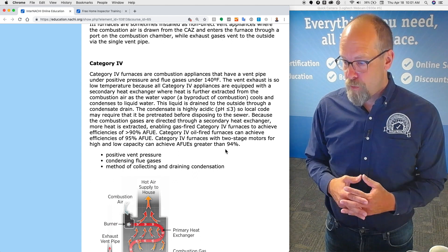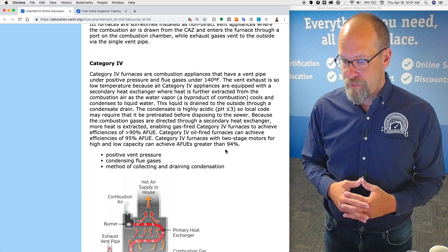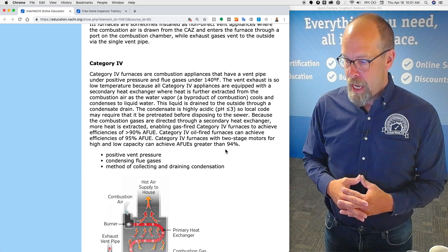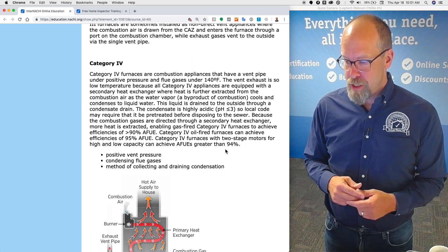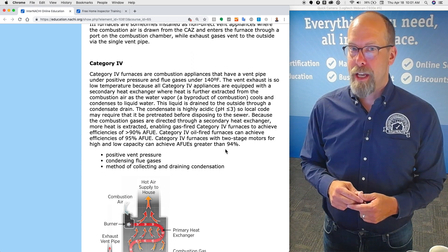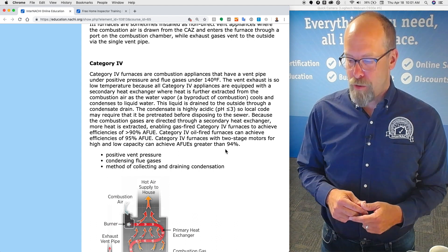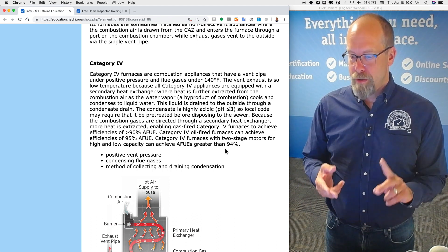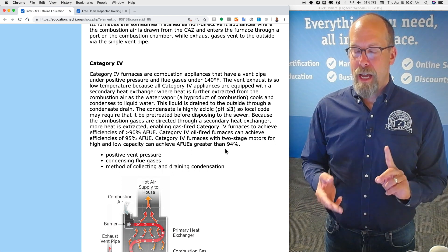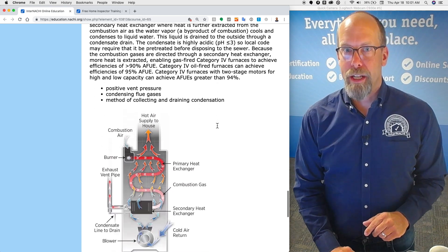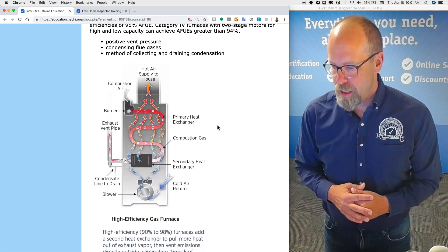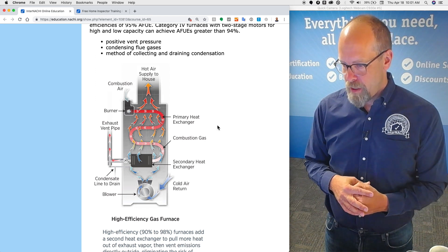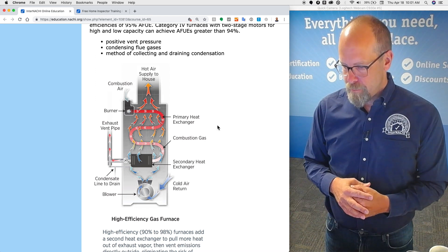Category four oil-fired furnaces can achieve efficiencies of 95 percent. Category four furnaces with two-stage motors for high and low capacity can achieve even greater than 94 percent. So positive vent pressure, condensing flue gases, and you need a method of collecting and draining the condensation. There is a little drawing of a category four furnace.